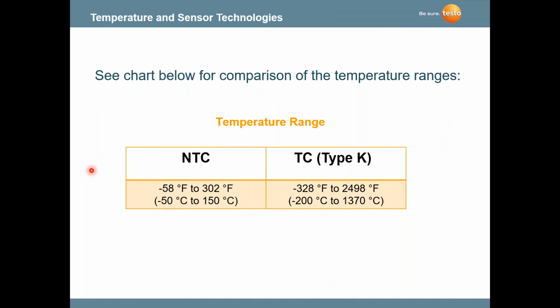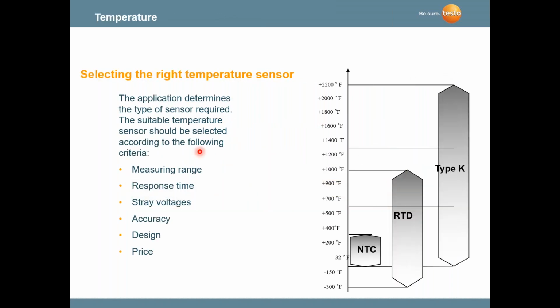And if you look at the NTC versus TC thermocouple, you'll see that there's a wide temperature difference. NTC is only good up to 300 degrees Fahrenheit or 150 degrees Celsius. NTC is a very accurate measurement to use on refrigeration and air conditioning systems. The thermocouple has a much wider range, up to almost 2,500 degrees Fahrenheit. We use K thermocouples a lot in our heating instruments, our combustion analyzers. But typically the preference today is for low temperature applications, NTC temperature technology is really the way to go.